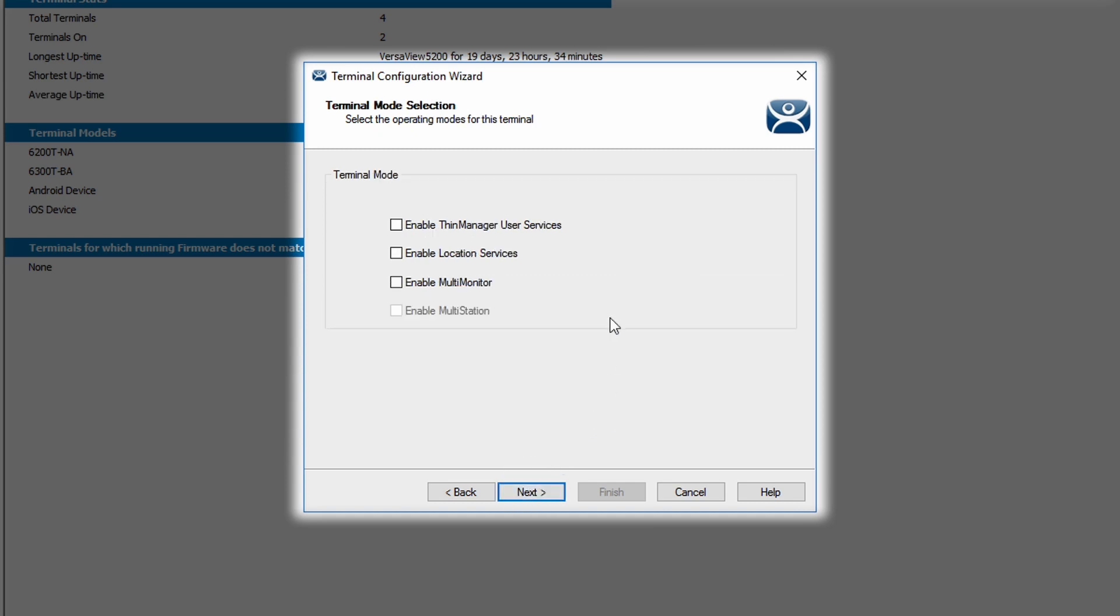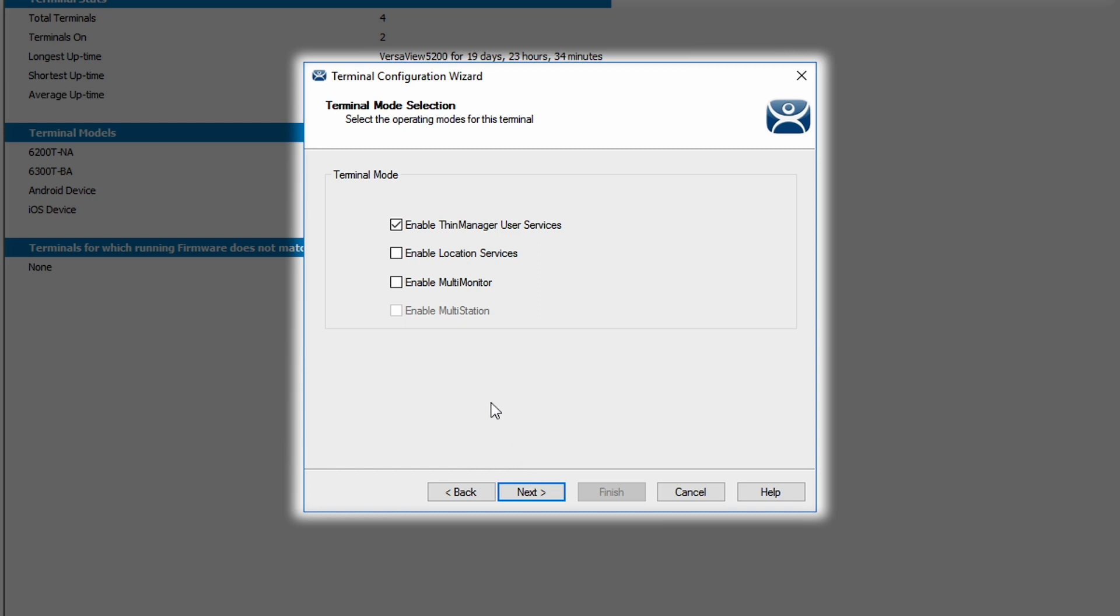Next is the terminal mode selection window. The first option is to enable ThinManager user services. This allows the terminal to react to user authentication, such as login or badge scan. The second option is to enable location services, which allows you to assign the terminal as a location in ThinManager. Multi-Monitor allows you to control multiple monitors and their layout if your thin client is capable of connecting and using multiple displays. Lastly, Multi-Station gives you the ability to use a single client to serve multiple defined stations and control them as desired.